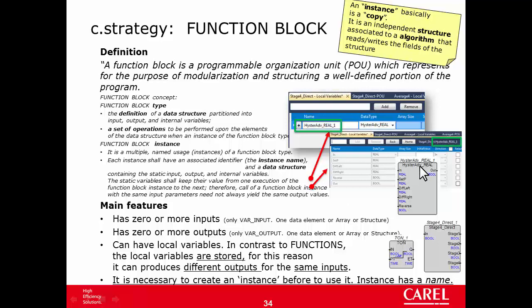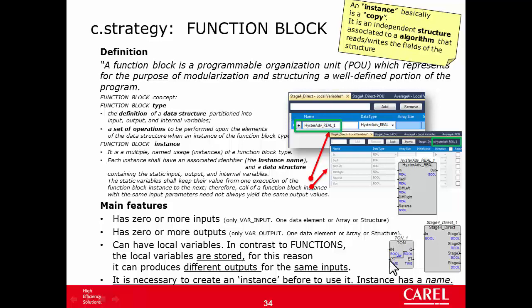So, each use of a function has its own set of input, output, local variable. So, since the variable is different, a function block can remember the value of the variable of the previous program cycle, as well as they can be different from other use of the same function block. And for this reason, they can produce different outputs for the same input. A typical function block is a timer, like the timer on, where the output can be false or true, depending on the time. And for an hysteresis block, the output can be false or true according if the input is around the set point and the input is increasing or decreasing.